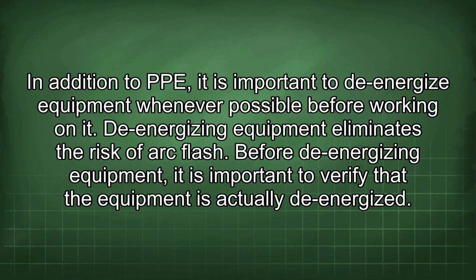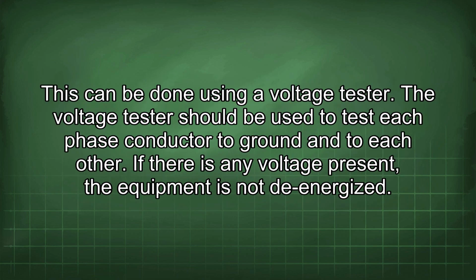Before de-energizing equipment, it is important to verify that the equipment is actually de-energized. This can be done using a voltage tester. The voltage tester should be used to test each phase conductor to ground and to each other. If there is any voltage present, the equipment is not de-energized.